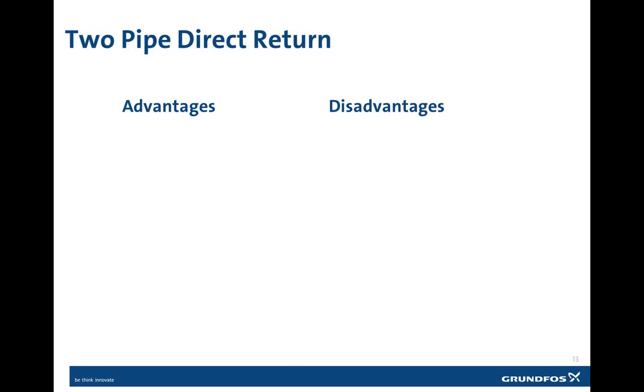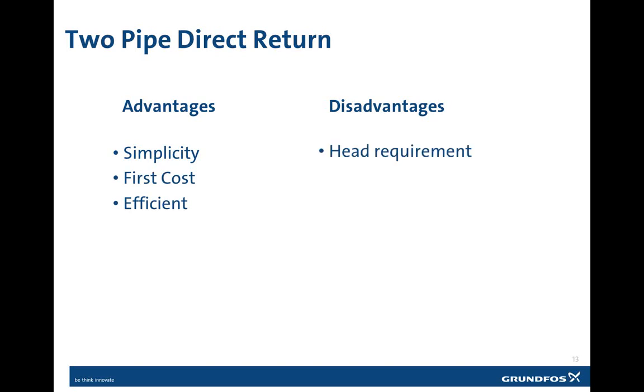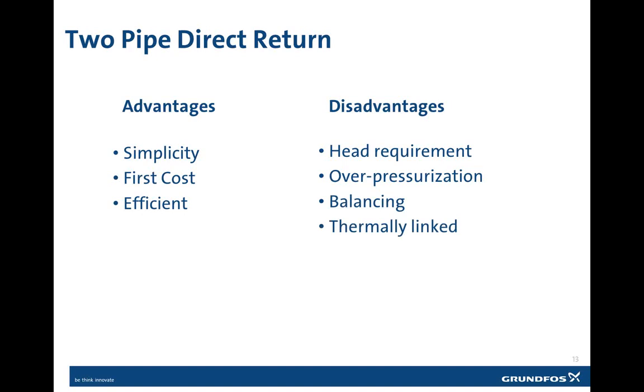Now, two-pipe systems do have both advantages as well as disadvantages. One of the main advantages is the simplicity of the design and the operation, and then the first cost: they are more cost effective for first cost installation, and they're efficient to operate. Now, some of the disadvantages would include the head requirement, because often there could be overpressurization of the zones that are located near the central plant. There could also be some challenges to balancing the system. Also, the systems are thermally linked, which means that all of the applications are subjected to the same supply water temperature.